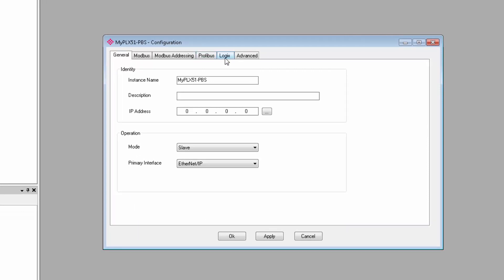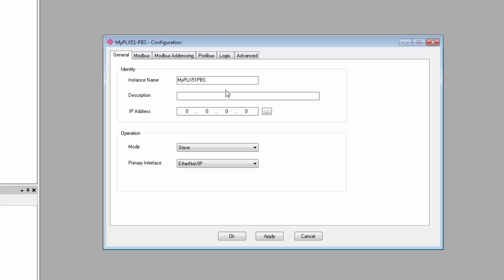and Logix tabs encompass the basic configuration for the gateway. The two Modbus tabs will only be enabled if that mode is selected, and at the time of this recording, it's not yet been released. On the General tab, you give the gateway an instance name. You can also give it a description if you like. Now, the instance name should match the name that you use in your RSLogix I.O. configuration. It doesn't actually need to match in order to work, but it simplifies things.